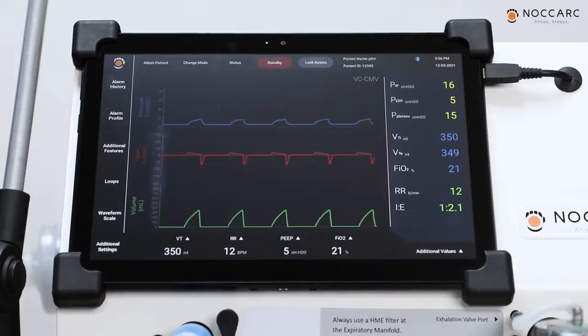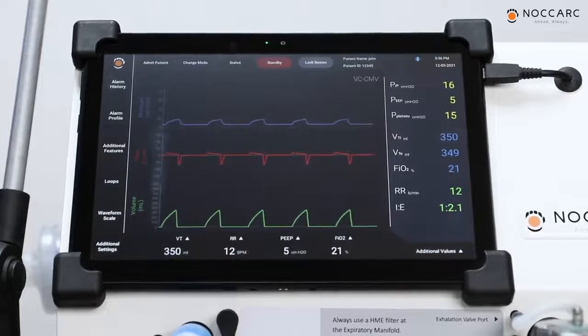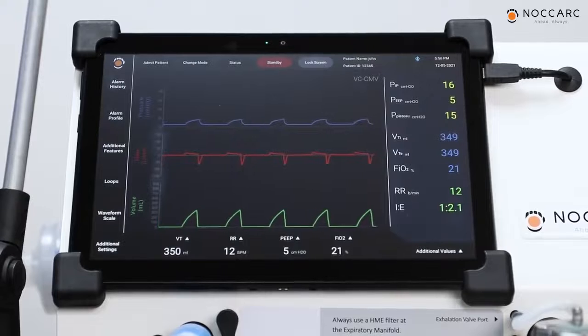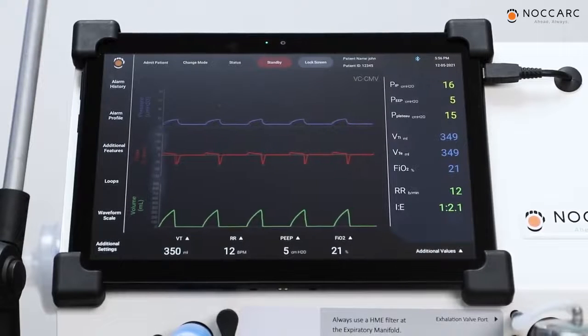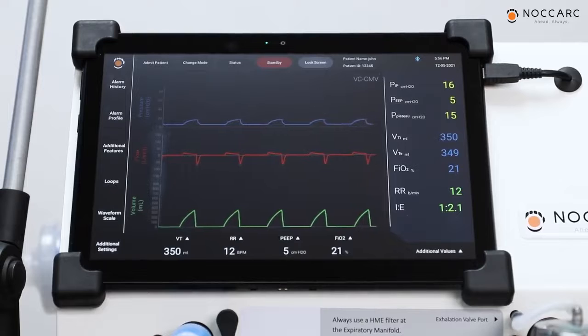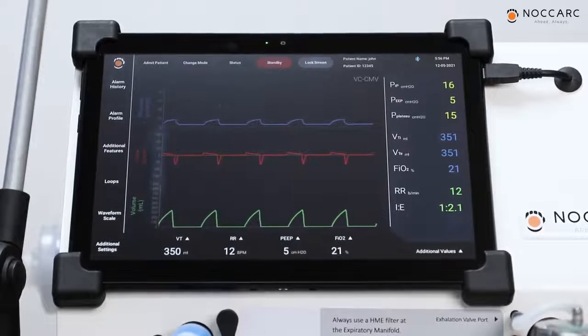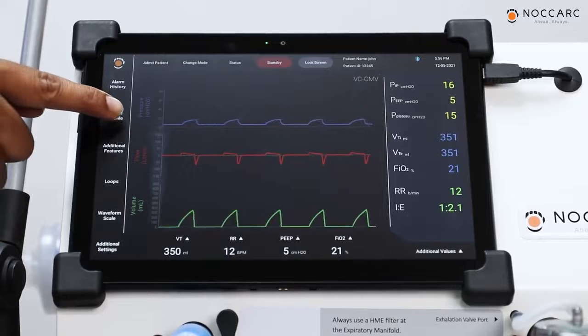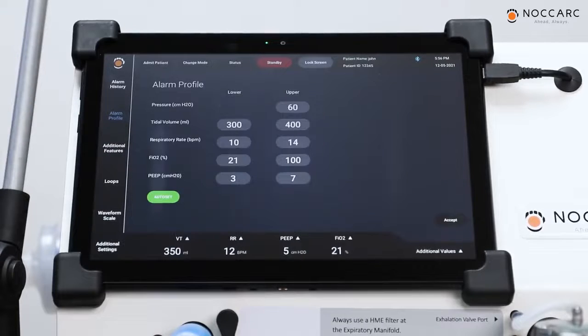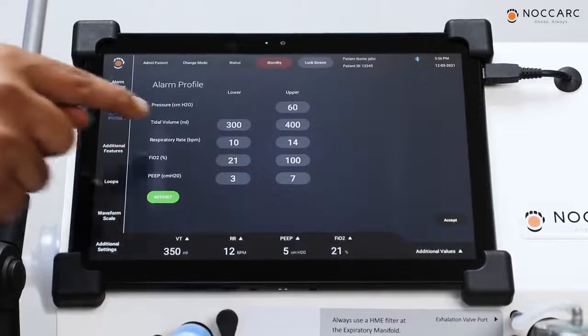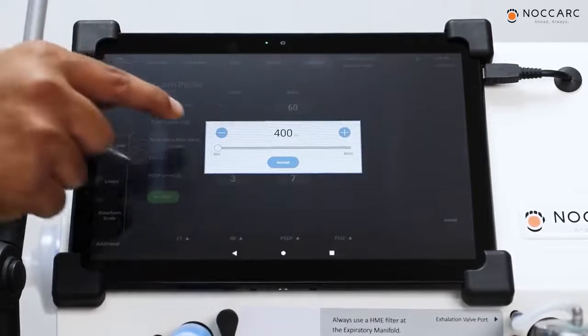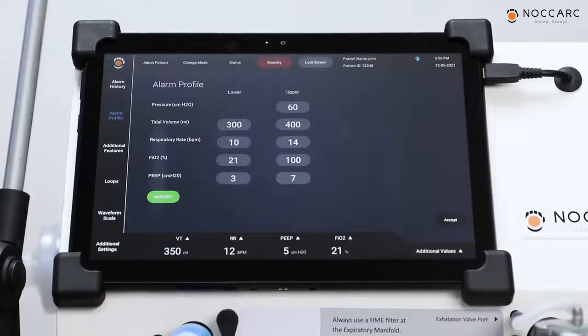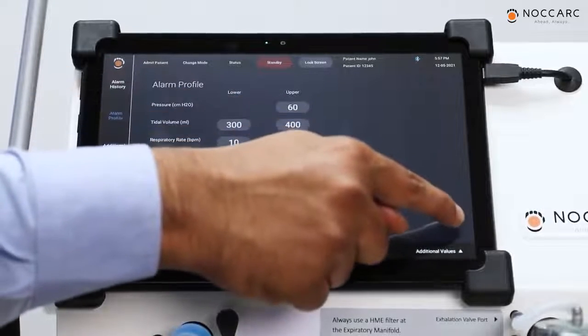If ventilator is used in emergency condition and user was not able to set the alarm profile during starting the ventilation, you can change the alarm profile by pressing this alarm profile button in the live operation. Select the parameters you want to change and accept it. Similarly, you can change all parameters. After setting the parameters, press on accept.